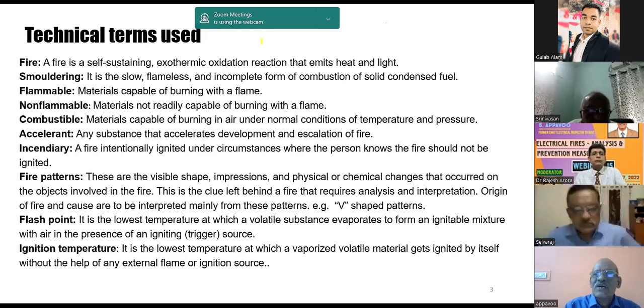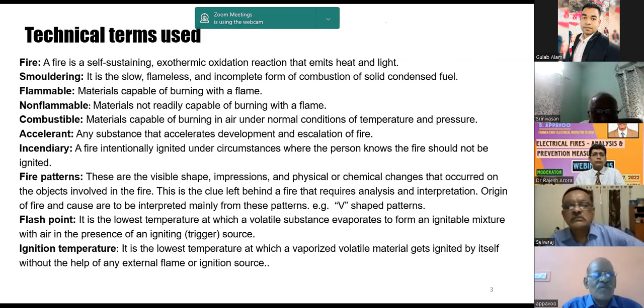Okay, before going into the case study, I would like to say a few definitions or technical terms used. You know that fire is nothing but a self-sustaining exothermic reaction. It emits heat and light, and smoldering is an important part. It's a slow, flameless, and incomplete form of combustion. For example, a mosquito coil will be smoldering, and camphor will be firing. So this is the difference between a smolder and the fire. Smoldering occurs whenever there is less ventilation or a deficit of oxygen.